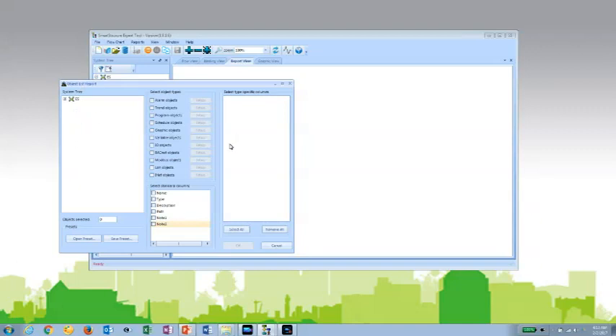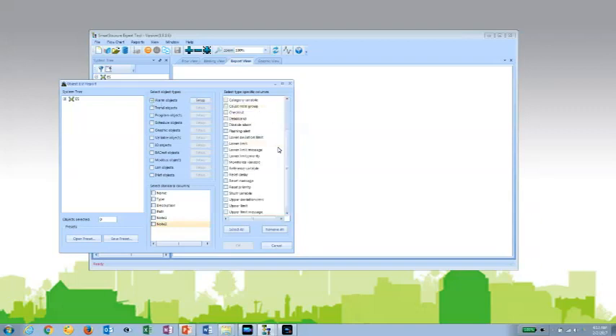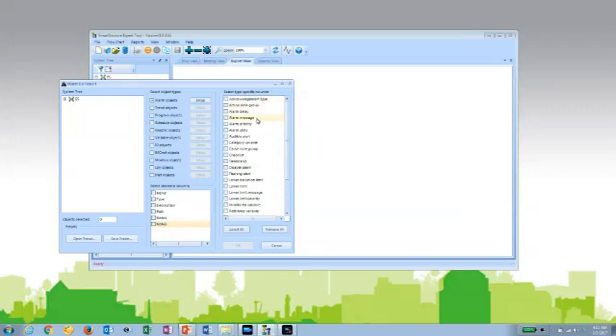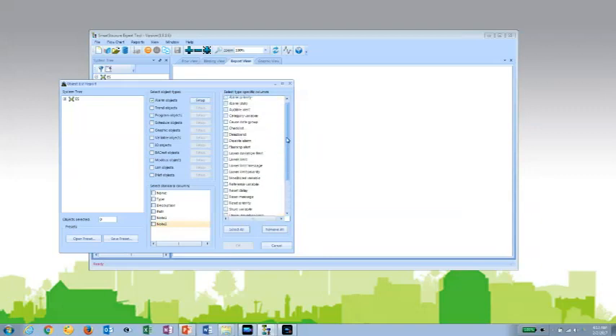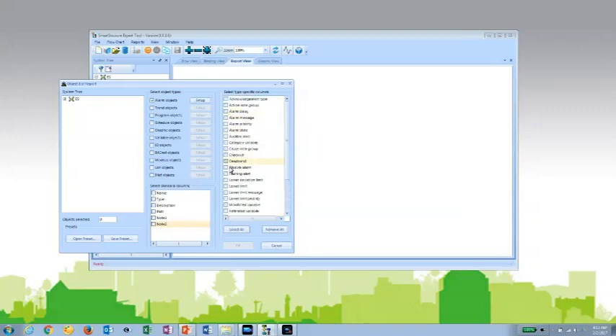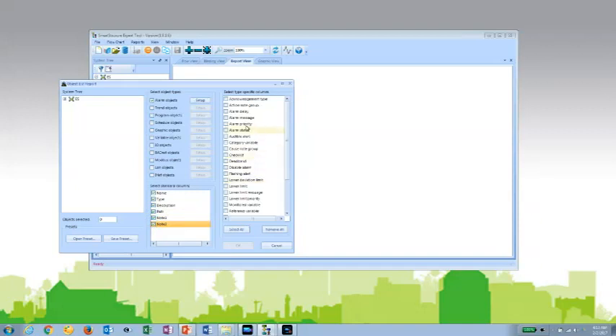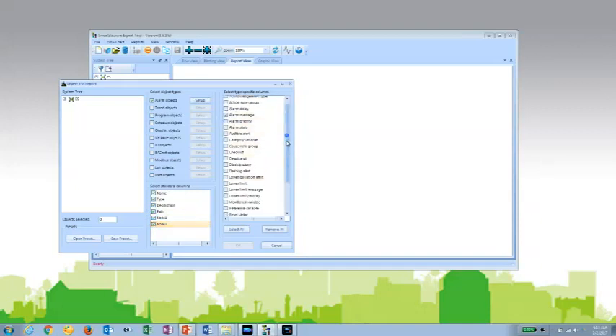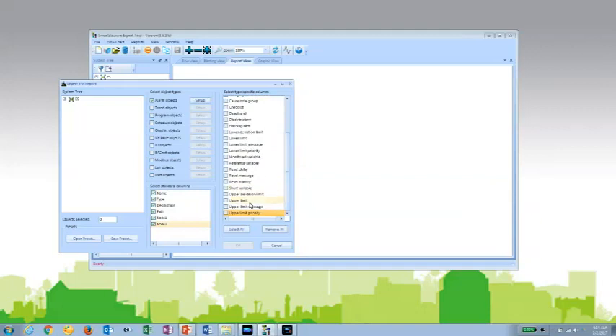Maybe in this case, to make sure all of our alarm messages are set up properly. I can click on the alarm objects, and you'll see that all the different parameters that are available show up here in my dialog. I could go through and pick exactly what ones, or all, of the different parameters I want to report on. I can also choose what standard columns I want to report on. So, let's say in this case, I want all my standard columns, and I want to report on all the different alarm messages. Since these could be both analog and digital alarms, I'm going to get all the different alarm messages that are available, including my reset message.